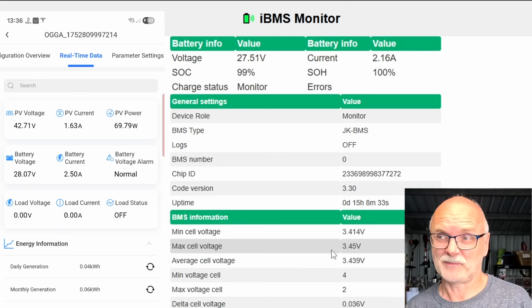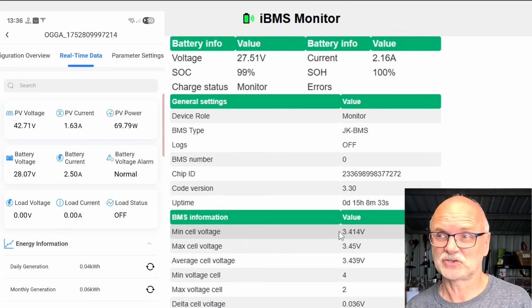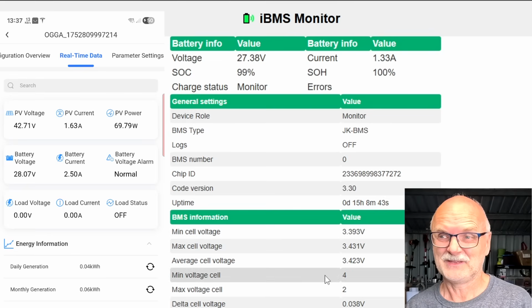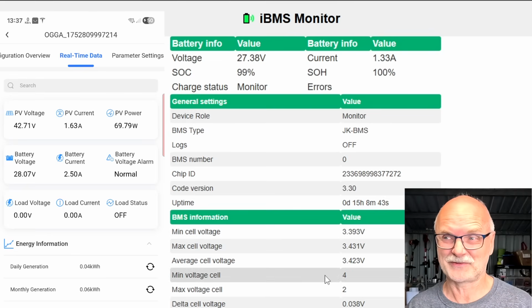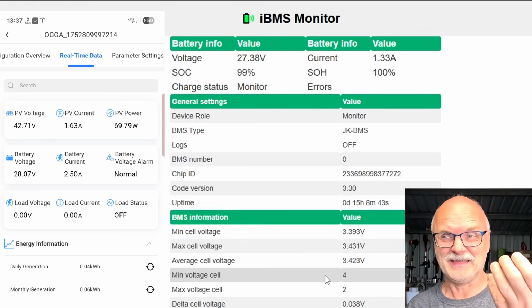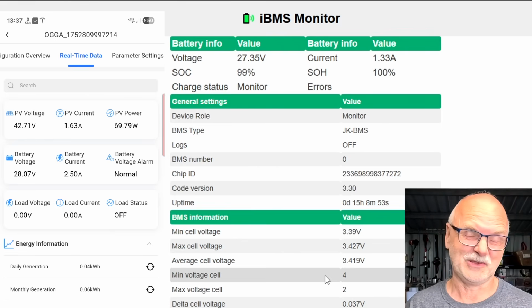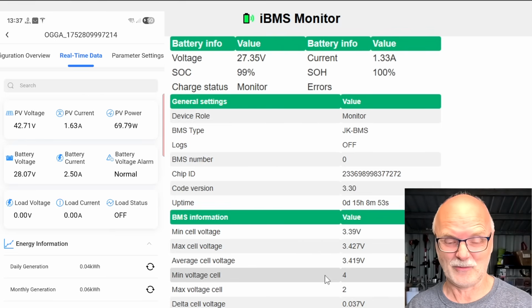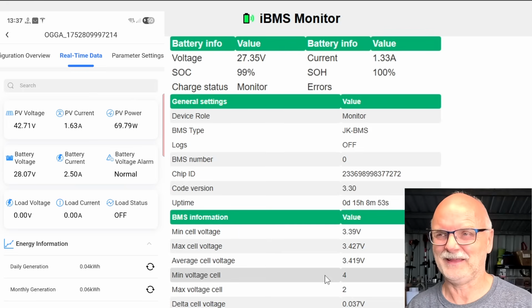Maximum cell voltage 3.45, minimum cell voltage 3.41, which is our cell number 4, unfortunately. You will see cell number 4 is always the lowest, and when we discharge this battery, you'll see cell number 4 is the lowest again. It stays always low. It's probably faulty, and I'll have to replace it as well.